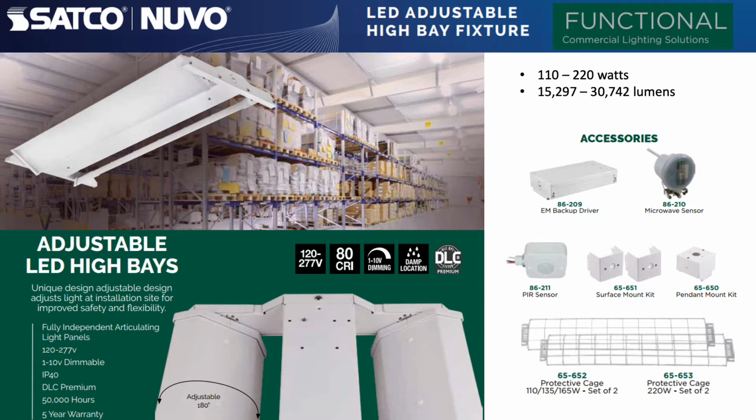When a linear high bay fixture is required, we have an adjustable high bay where the adjustment allows for unique beam spreads to fit the application. That's done by turning the two outside LED modules on the fixture either in and out, as both are rotatable 180 degrees. Fixture packages start at 110 watts and go up to 220 watts, with lumen packages as low as 15,000 or more than 30,000 lumens. Pick the right lumen package to meet your foot candle level. We certainly don't want wasted energy used where it's not needed.